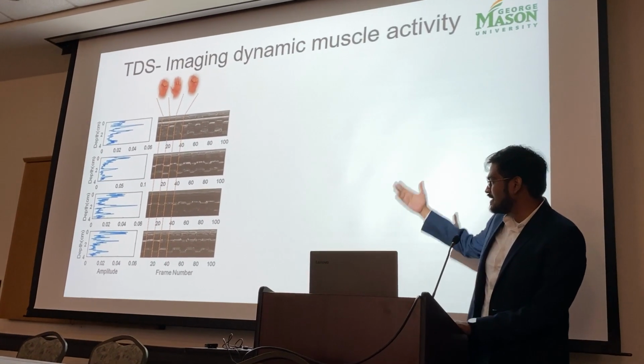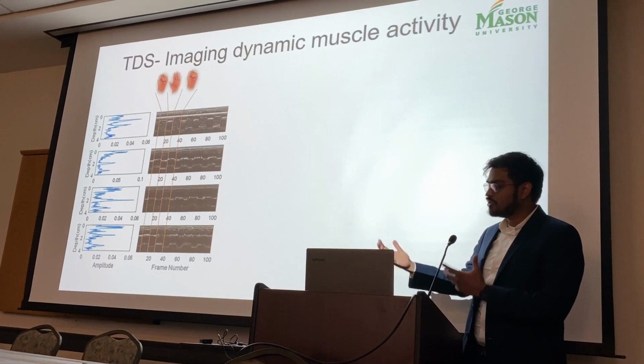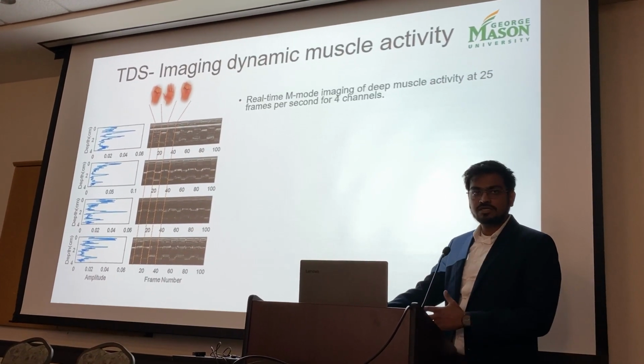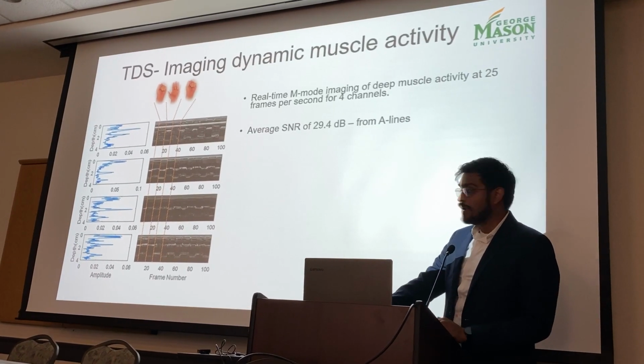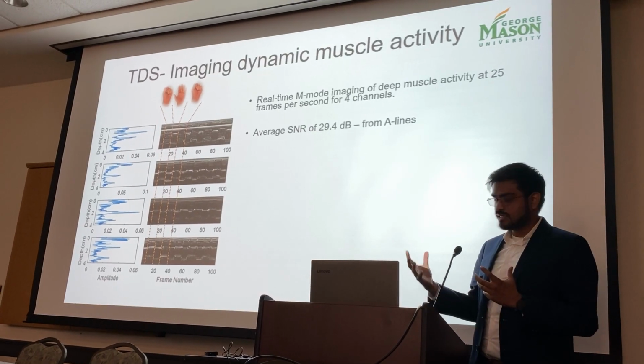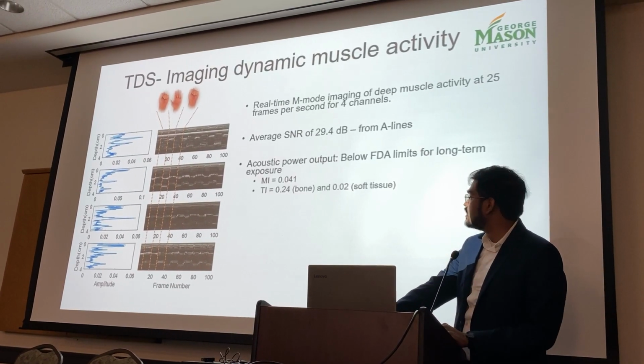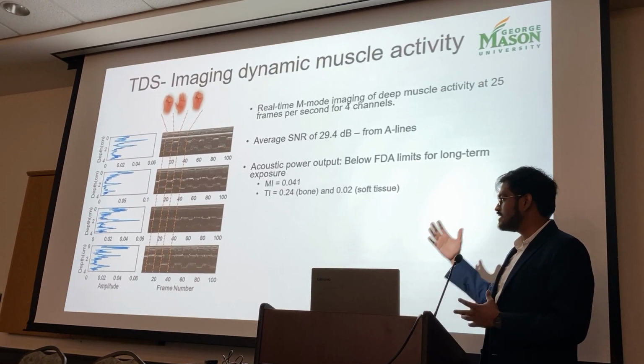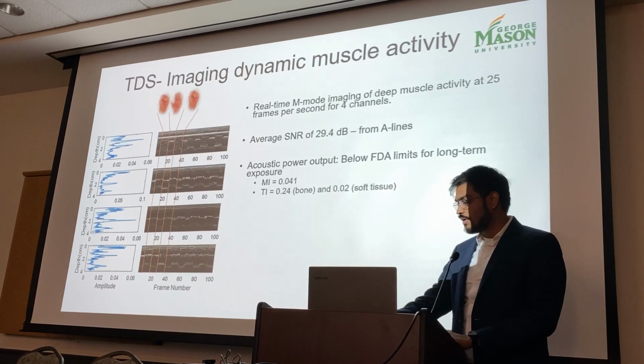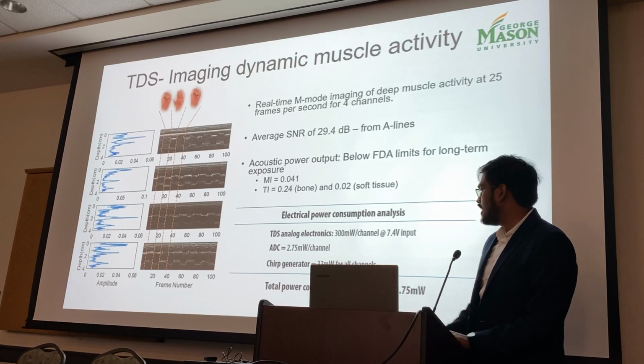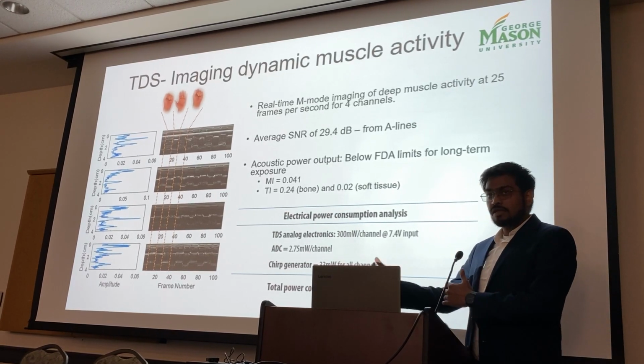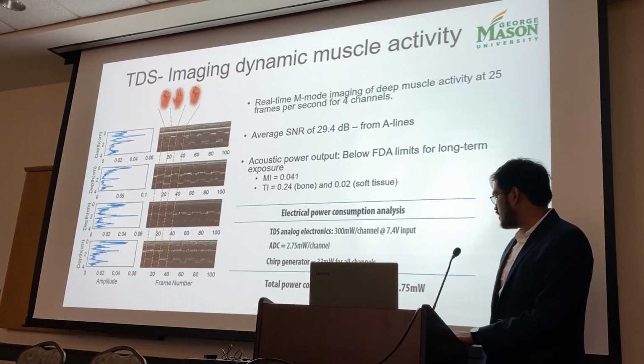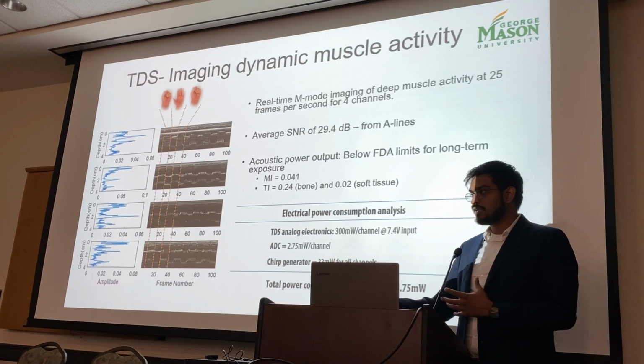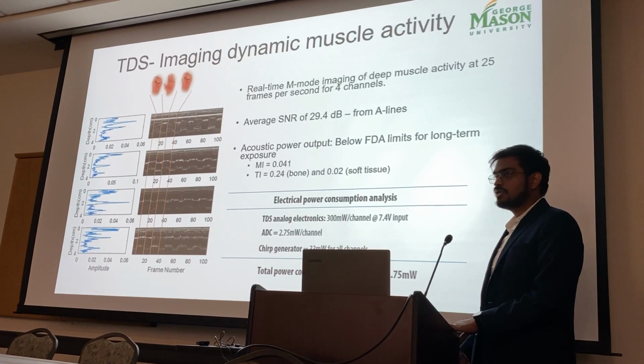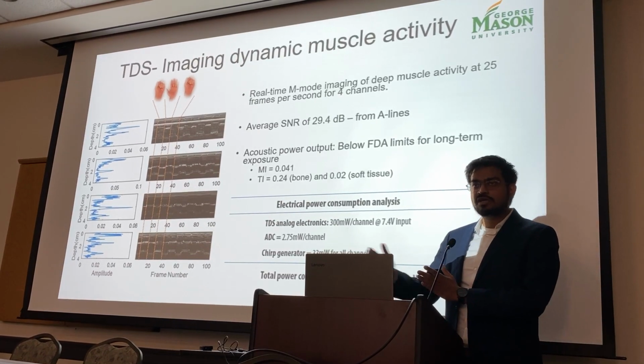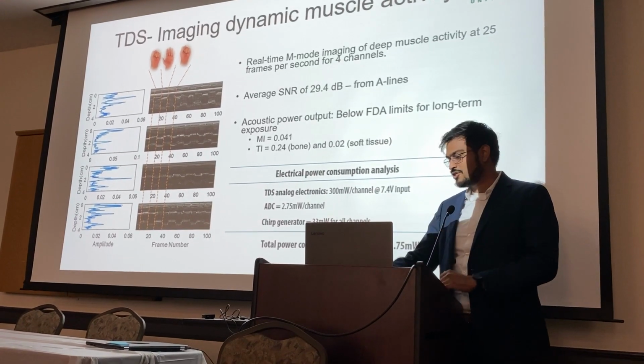So what we're basically trying to show with this image is that as you do different motions, these patterns emerge out of these motions, and we can do this real-time imaging at about 25 Hertz, which is sufficient for most applications, beyond prosthetic control actually. And we get really nice, robust signal-to-noise ratio of about 30 dB. We have shown that these sensors are safe for long-term use and well below clinical regulatory standards set by the FDA. Power consumption is still a little bit high, and we would like to bring it down, but it's still within the range where we can operate it off of a prosthetic battery. With a typical 4,000 milliampere hour battery, it would take about 10% of the battery life, which is negligible compared to what the hand would actually be consuming.